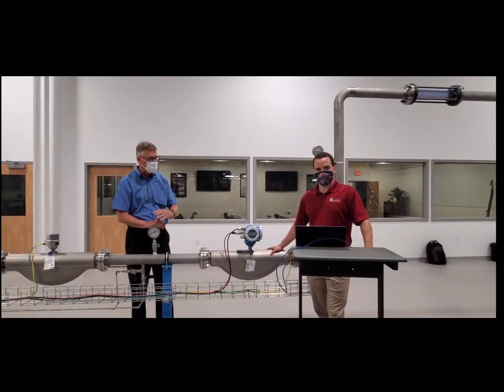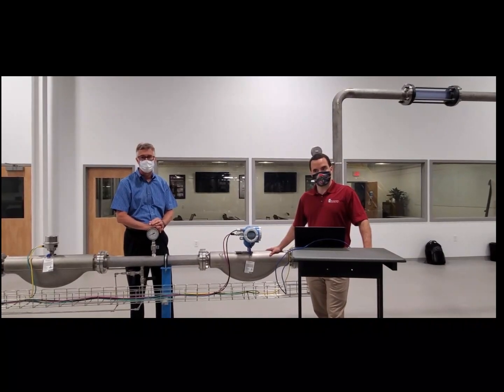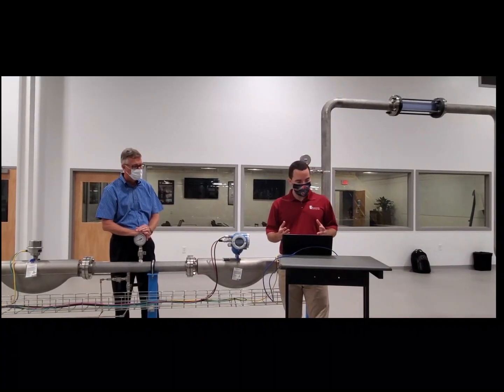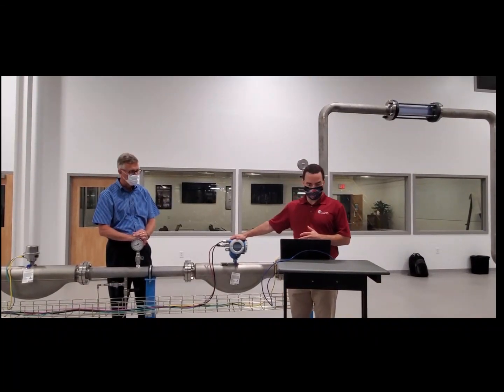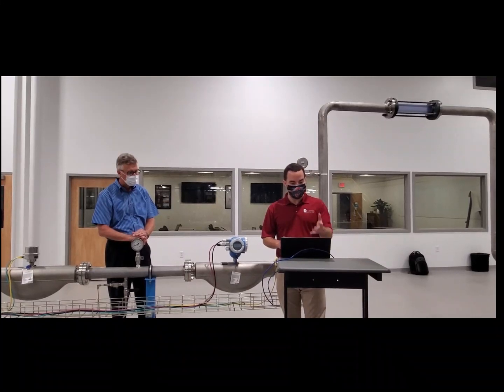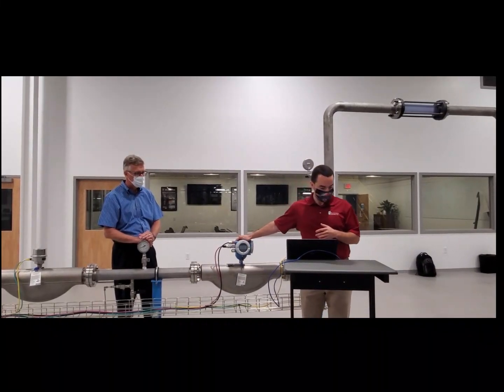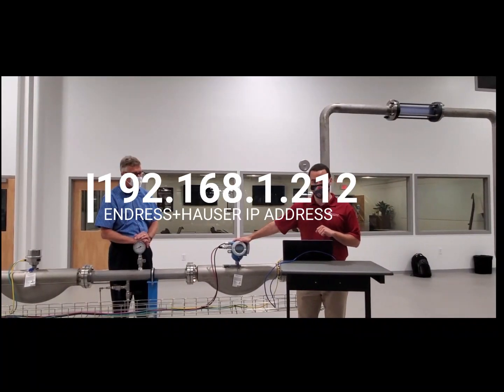This is Bill Wolf, back here with Trent Kilpogrand, and we're going to run through our Mission Impossible of going through a Heartbeat with our F-Series Coriolis meter. With Heartbeat technology, you can access it via a hardwired Ethernet connection or wirelessly to your Promass transmitter. You can do it from a laptop. The first thing you want to do is make sure you add the transmitter Ethernet IP to your laptop. Endress+Hauser has the same universal IP address for all transmitters — it's 192.168.1.212.